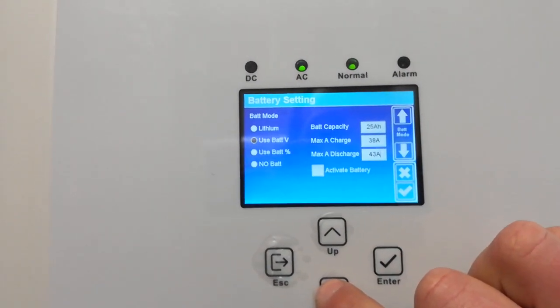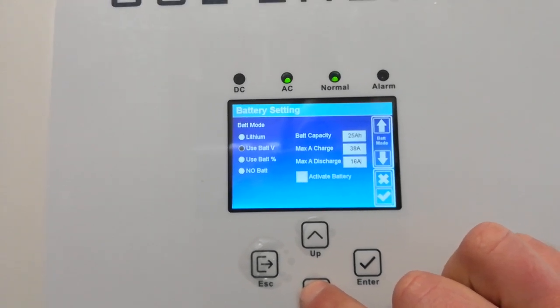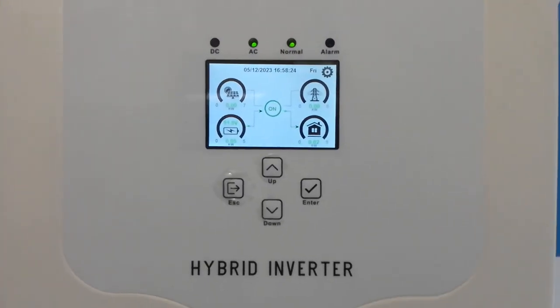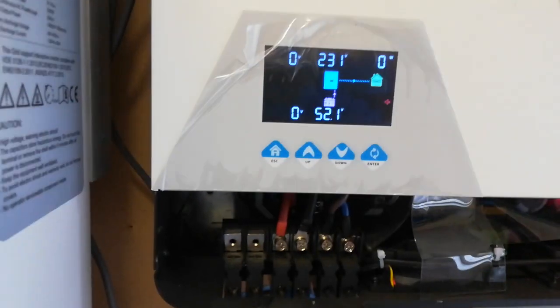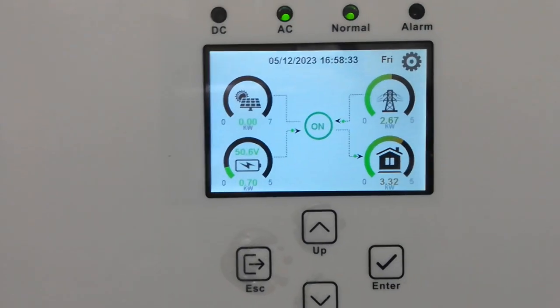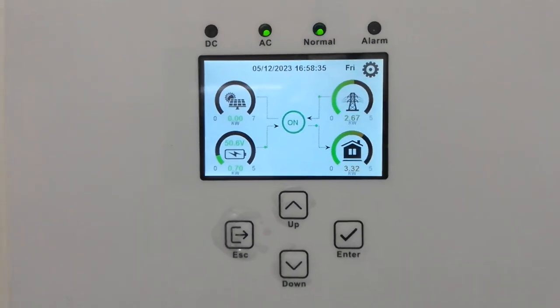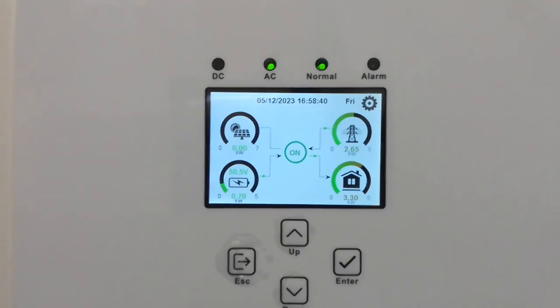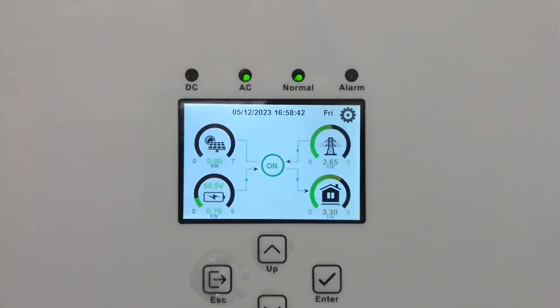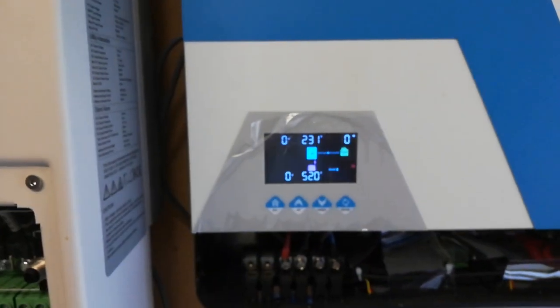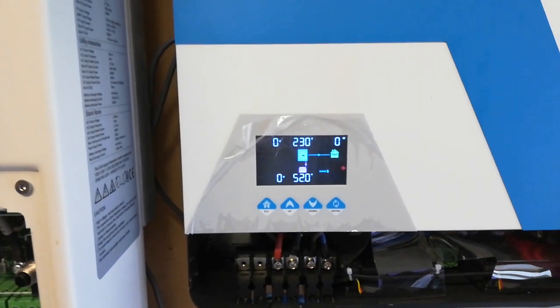This is just limiting how much current goes into — or how much power this inverter can contribute. Again, pretty slow but not too bad, and then all the CT ratios are wrong again. I don't really understand why, in that certain configuration, the CT ratio actually makes a difference to the speed at which it can control the input on this inverter.